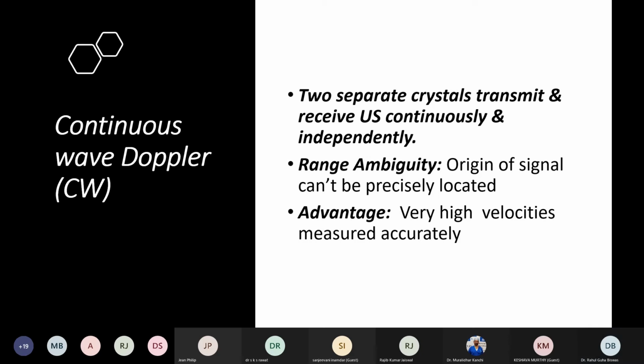So the pulse repetition frequency problem for fast moving structures or high velocity areas is dealt with an application called continuous wave Doppler. What we do here is basically we use two sets of crystals. One set keeps on sending sound waves. They are the messengers, they are the transmitters, and the other set of piezoelectric crystals only receive. They are not sending out anything, they are not waiting for anything to come back. They are just receiving.